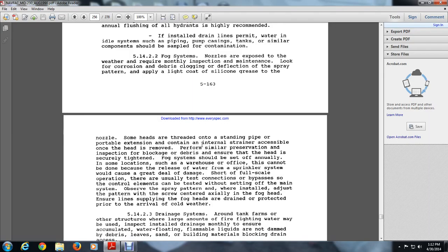In some locations, such as a warehouse or office, this cannot be tested because the release of the water sprinkler system would cause great damage. Short of full scale operation, there are usually test connections so the control elements can be tested without setting off the main system. Observe the spray pattern when installed and adjust the pattern by the screw center on the fog head, ensuring the line supplying the fog heads is drained and protected prior to the arrival of cold weather.